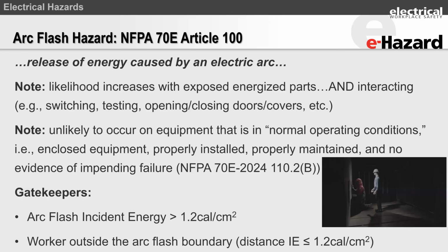And so what they're saying is that if you do maintain your equipment, and if it's in a normal operating condition, where, I mean, you can read that, then it's unlikely for an arc flash to cause injury. But the gatekeepers for when an arc flash becomes hazardous is when the arc flash energy is greater than 1.2 calories per square centimeter, or when the worker is outside of the arc flash boundary.